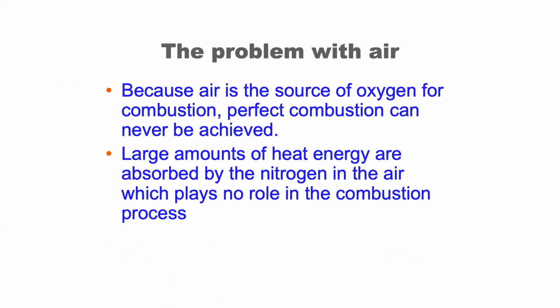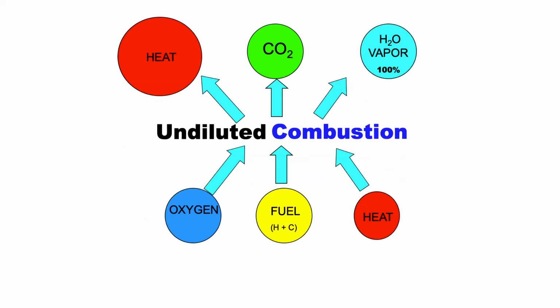So because air is the primary source for the oxygen in combustion, you can never get to perfect combustion because you always have that extra nitrogen flowing through. Large amounts of heat energy are also absorbed by the nitrogen, and they're entrained or carried through, and they play no role in the combustion process, but they're carried through as part of the exhaust into the flue gas exhaust.